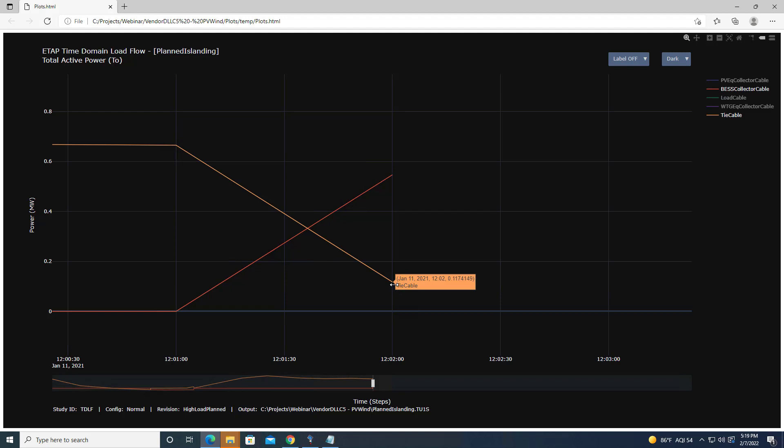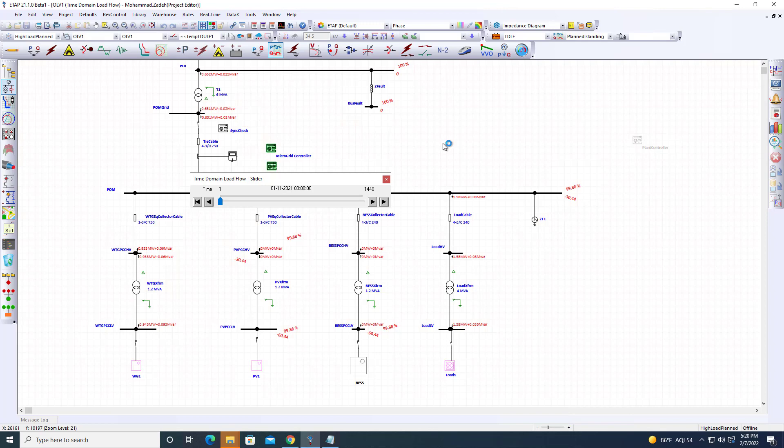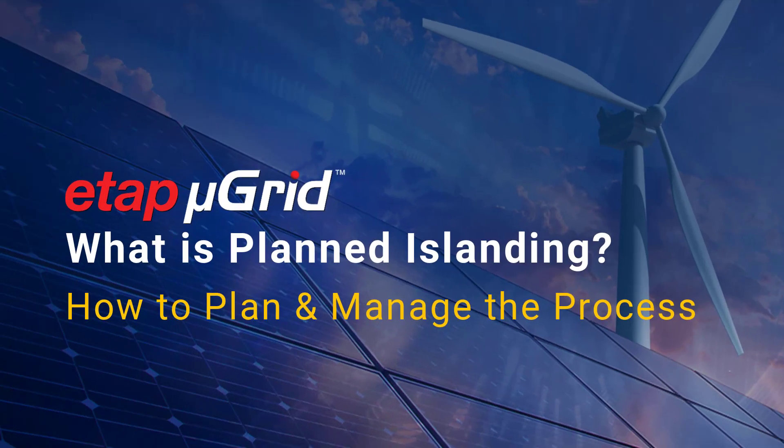When it reaches a certain level with a dead band around 100 kilowatts, the next time step—about five seconds later—islanding can occur. This demonstrates an important microgrid function: whenever we want seamless planned islanding, we can use this planned islanding approach. Thank you for your attention.